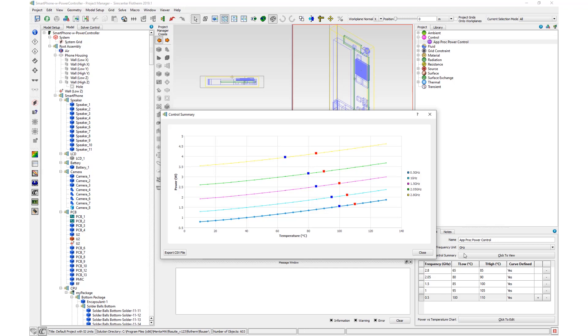For a transient analysis, if t-sensor is higher than t-high, then the controller switches to the next lowest defined frequency. The frequency is updated once every time step.